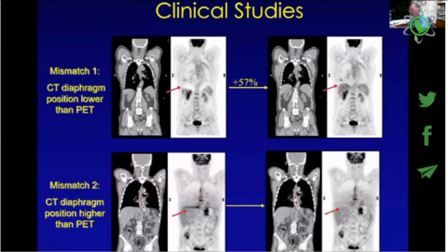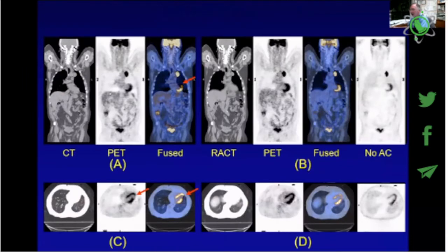Whether you do that in oncology type application or in cardiac type application, you can see here that the PET and the CT are not properly matched. You can see the heart on the PET image is not overlaid properly on the CT image. And as such, when you go look at different axial slices, it appears as if the patient has an infarct, but in reality, that is primarily because of the mismatch between the PET and the CT.